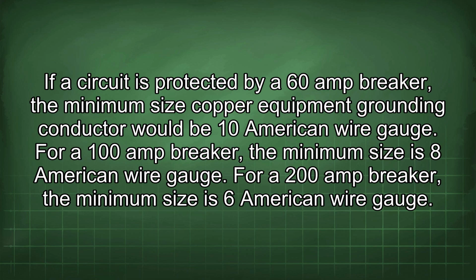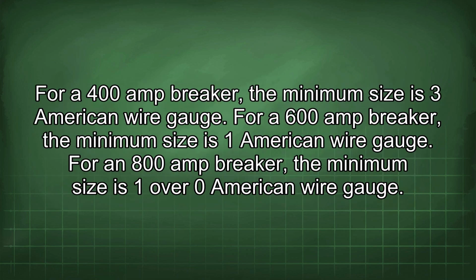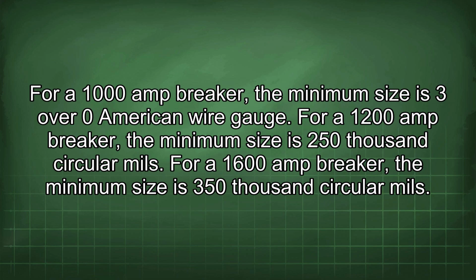For a 200 amp breaker, the minimum size is 6 American wire gauge. For a 400 amp breaker, the minimum size is 3 American wire gauge. For a 600 amp breaker, the minimum size is 1 American wire gauge. For an 800 amp breaker, the minimum size is 1/0 American wire gauge. For a 1000 amp breaker, the minimum size is 3/0 American wire gauge. For a 1200 amp breaker, the minimum size is 250,000 circular mils.